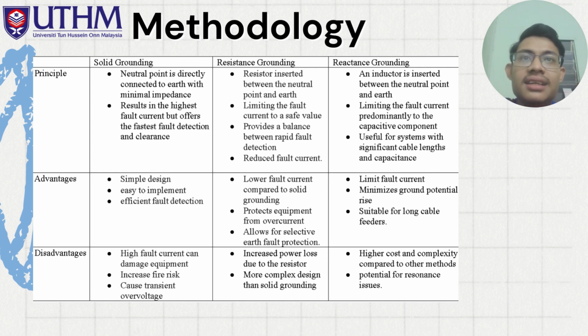And lastly is reactance grounding. An inductor is inserted between the neutral point and earth, limiting the fault current predominantly to the capacitive component, useful for systems with significant cable lengths and capacitance. The advantages are that it can limit the fault current, minimize ground potential rise, and is suitable for long cable feeders. Lastly, the disadvantages are higher cost and complexity compared to other methods, and potential for resonance issues.